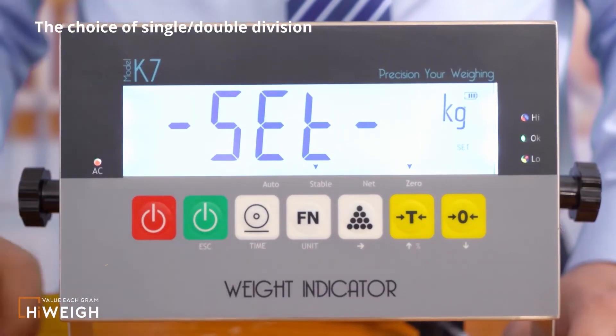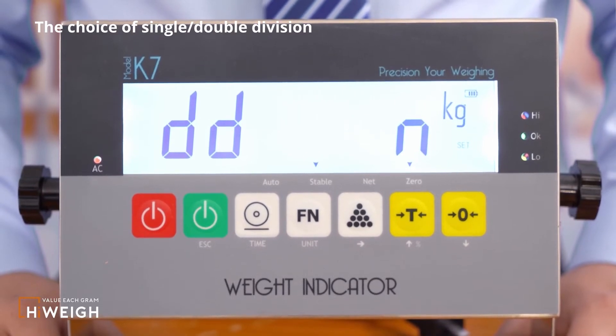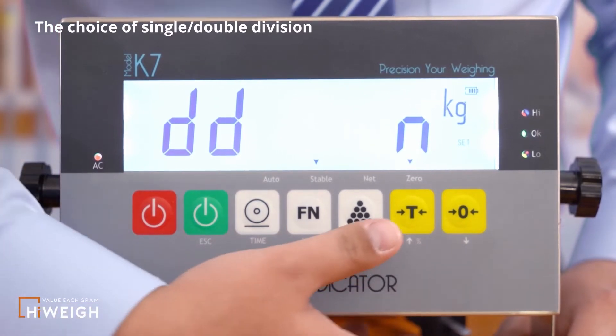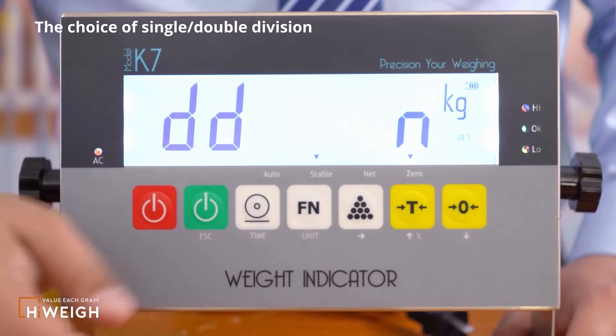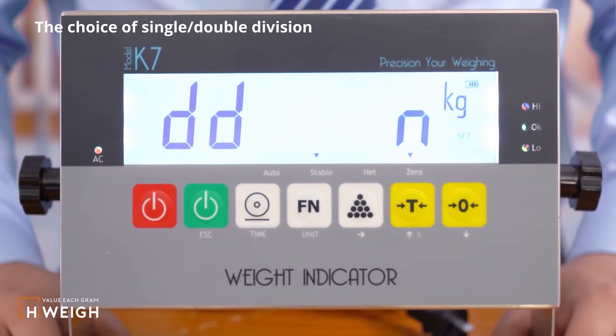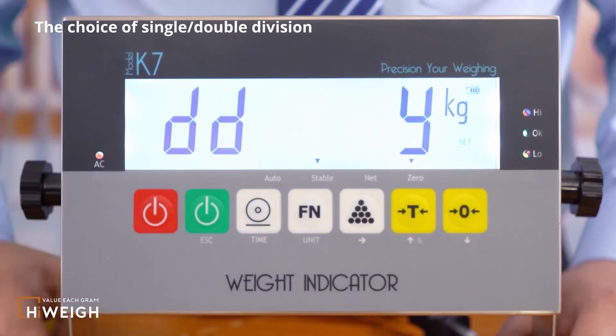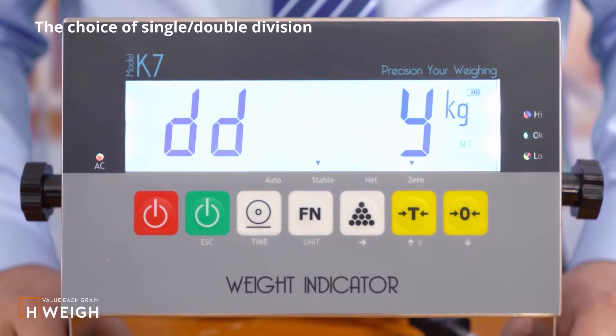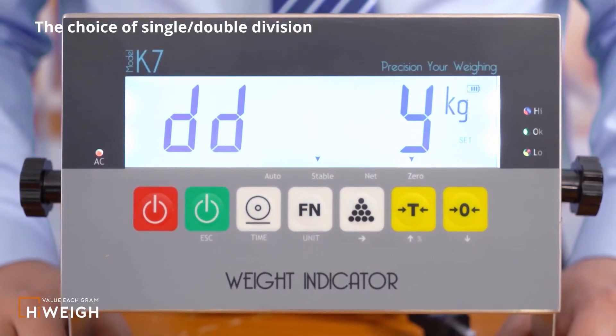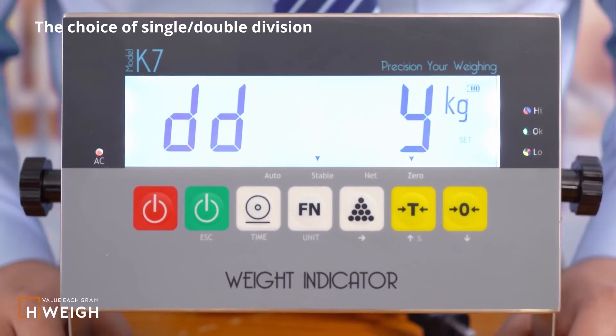After displaying the set interface, press the accumulation button to enter. The first option is the choice of single or double division. Press the tare button or the zero button to select. Selecting DD as n means single division — the division value across the entire capacity is fixed. Selecting DD as Y means double division — there will be a configuration of a conversion point, and the capacity will be divided into two parts with different division values for each part. I choose double division to demonstrate. Press the function button to save.